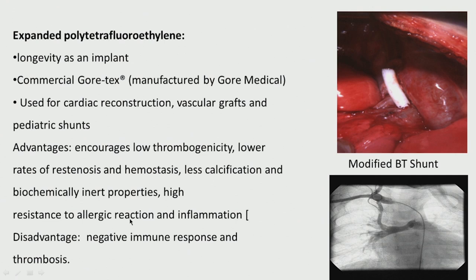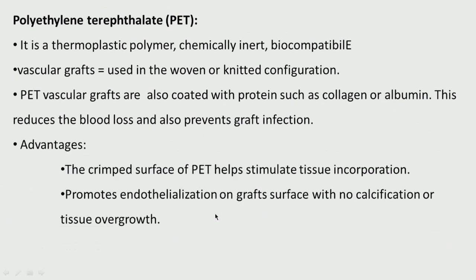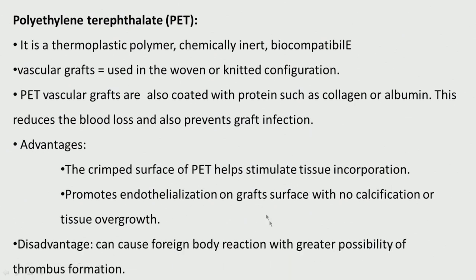Disadvantages of ePTFE include negative immune response and thrombosis. PET is chemically inert and biocompatible. It is used in large-diameter vascular grafts — it is woven and you can coat it with protein, collagen or albumin to reduce blood loss. The crimped surface of PET helps stimulate tissue incorporation and promotes endothelialization on the graft surface with no calcification. However, it can create a foreign body reaction with greater possibility of thrombosis formation.